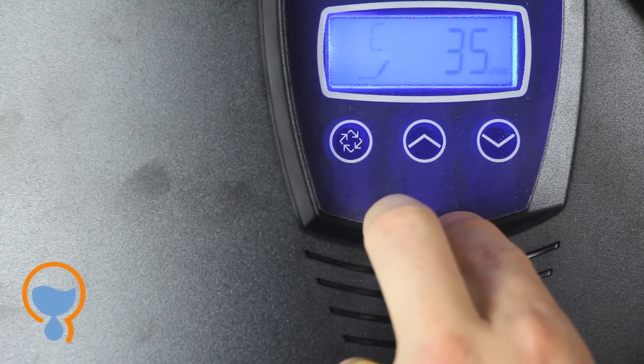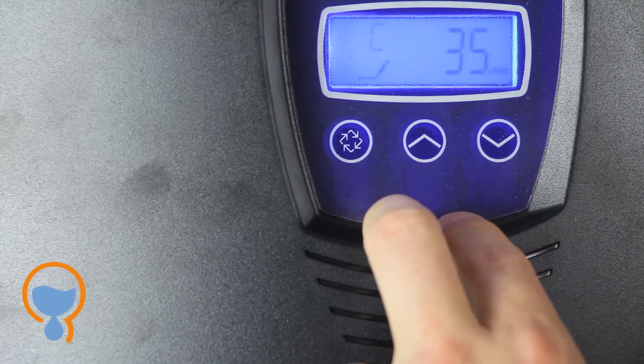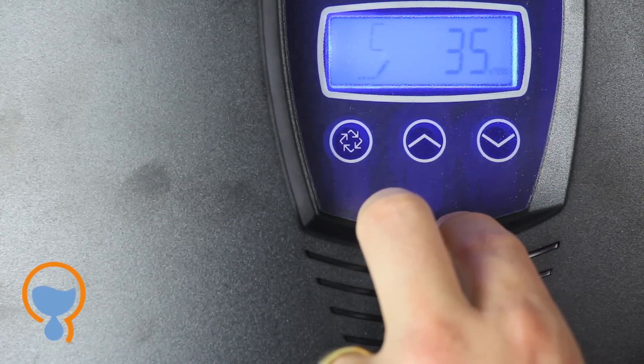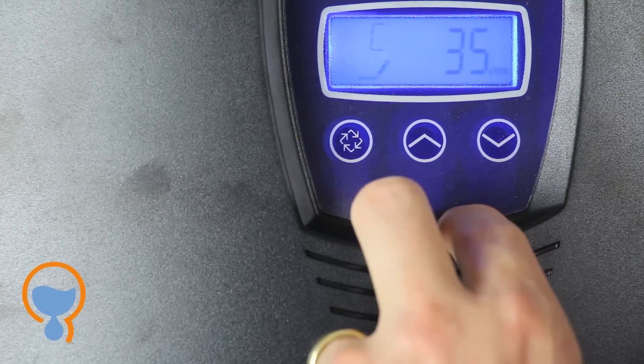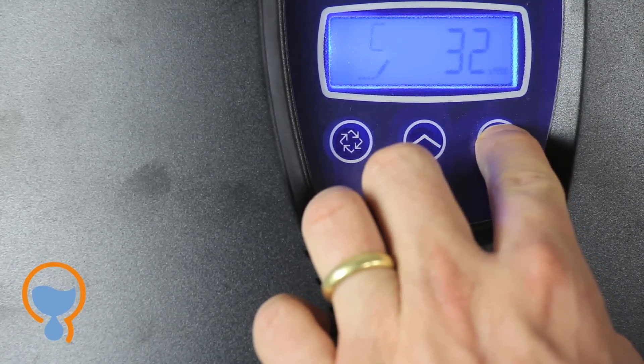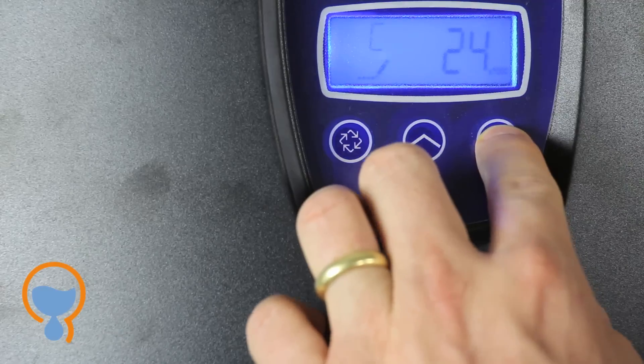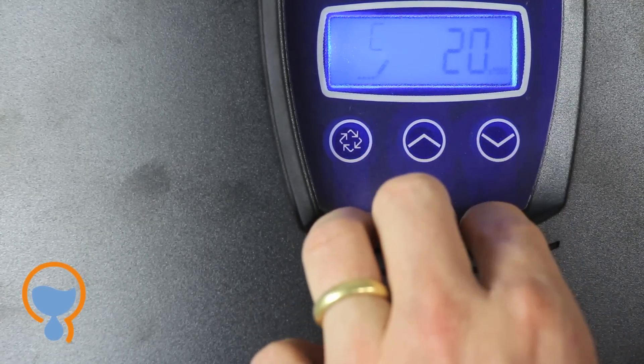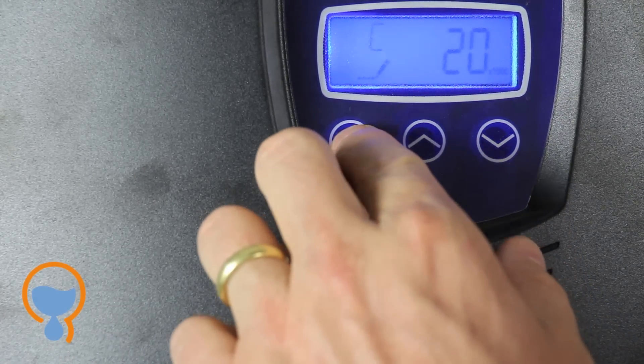The capacity. The capacity that we program in depends on the size of the water softener that you purchased. In this case we're going to assume that this is a one cubic foot unit. So we're going to program the capacity to the highest salt efficiency settings which in this case is 20 times 1000. Press enter.